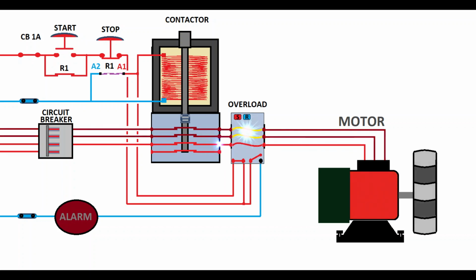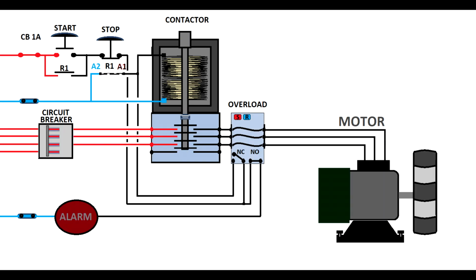So because one phase is unbalanced, now the motor starts suffering, it starts to overheat, but also the overload will pick up this problem and will allow the motor to run until the peak is reached, where the overload will interrupt the circuit. So just to make it a little bit clearer, when you fit a motor into a system, the motor has a badge, and on that badge you will see the motor's running amps. So when you set up the overload, it must match the motor's amps consumption.